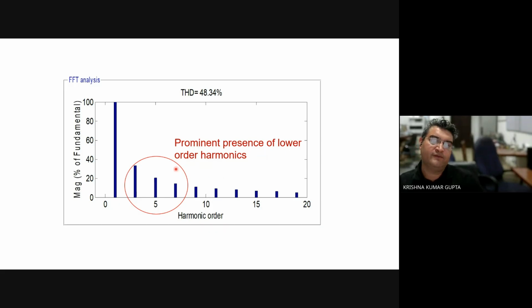So the kind of filter we require here is a low pass filter, which should pass the 50 hertz fundamental component and block the other components. It is difficult to filter out lower order harmonics because the amount of inductance or capacitance required will be very large. You will need large filters there.